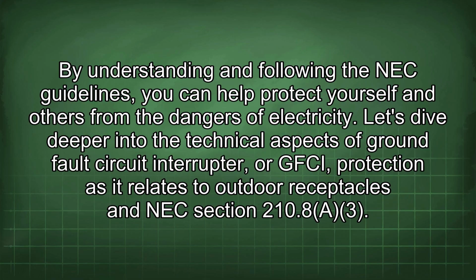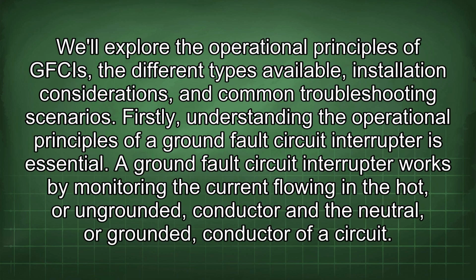Let's dive deeper into the technical aspects of ground fault circuit interrupter, or GFCI, protection as it relates to outdoor receptacles and NEC section 210.8 A3. We'll explore the operational principles of GFCIs, the different types available, installation considerations, and common troubleshooting scenarios. Firstly, understanding the operational principles of a ground fault circuit interrupter is essential.